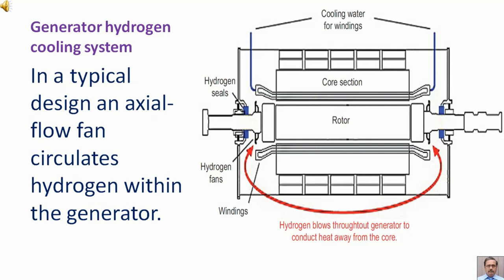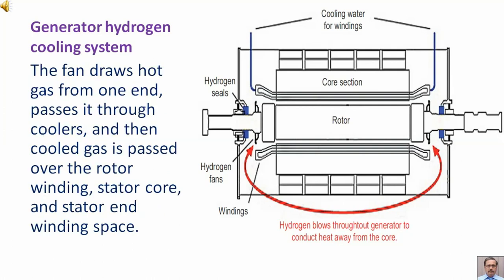In a typical design, an axial flow fan circulates hydrogen within the generator. The fan draws hot gas from one end, passes it through coolers, and then cooled gas is passed over the rotor winding, stator core, and stator end winding space.